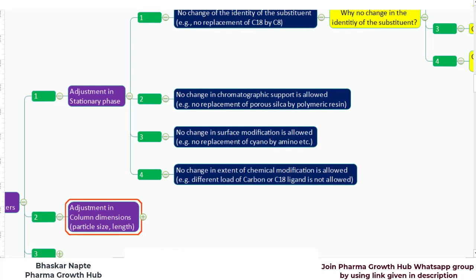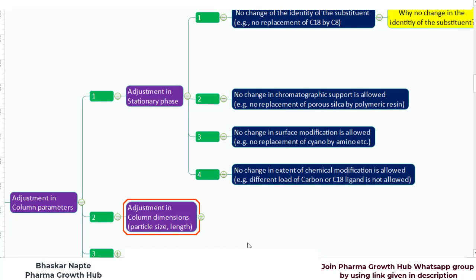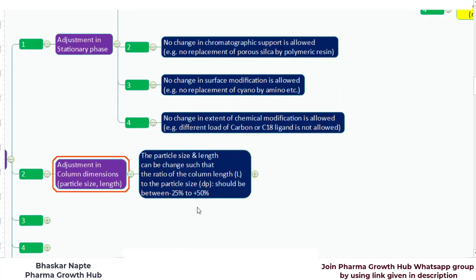The second point when it comes to liquid chromatography column parameters is the adjustment in column dimensions — specifically particle size and length. The guidance provided by USP General Chapter 621 is: the particle size and length can be changed such that the ratio of column length (L) to particle size (DP) should be between minus 25% and plus 50%. The ratio must be maintained in the range of −25% to +50%.